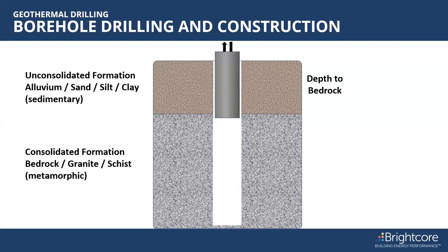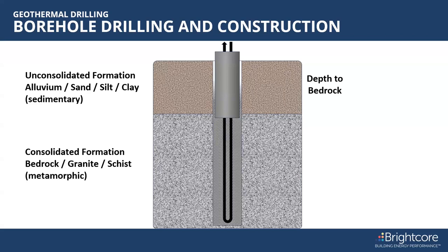From there we run high density polyethylene tubing, which is flexible and durable pipe. Depending on location it varies; in New York it was usually about 499 feet or you needed a mining permit, whereas Massachusetts restrictions aren't as strict. The drop-off in pumping power versus how much actual energy is stored or taken in becomes a big factor in how we assess projects based on depth to bedrock.